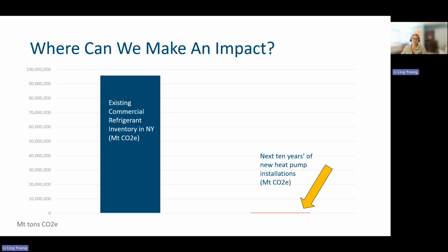In the coming years, the number of heat pumps installed in New York and Vermont, as I just showed, is going to be between 40 and 50,000 heat pumps a year. The climate impact of those new installations is that teeny bar on the right, and it hardly even registers at all in the face of the carbon dioxide equivalent of the refrigerants that have already been installed and are out there now. We have to do something about that tall blue bar on the left, while at the same time building new leak-tight systems. We don't want the new systems to be a liability in the future.